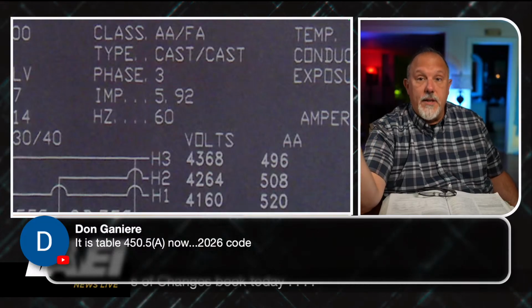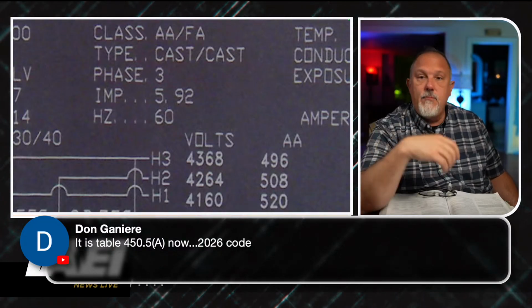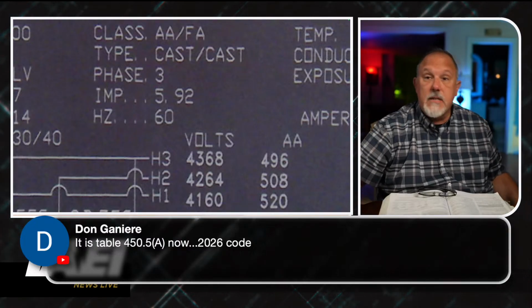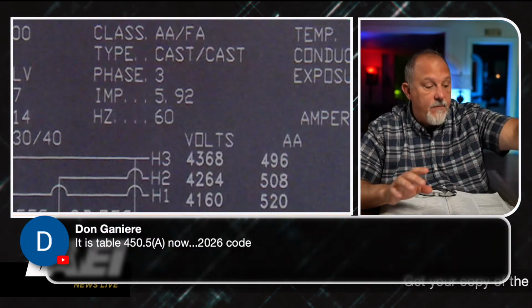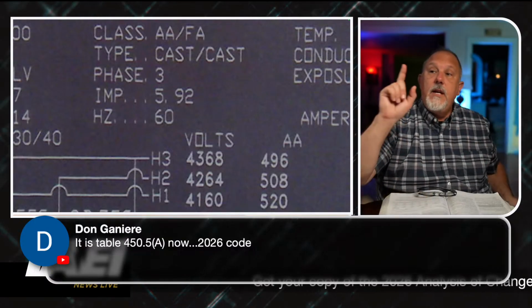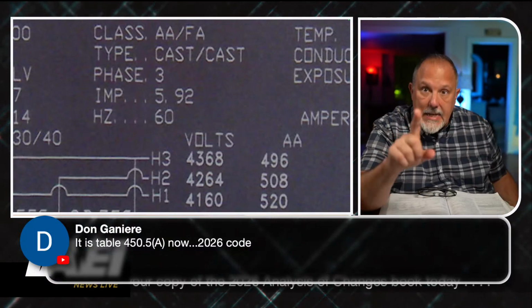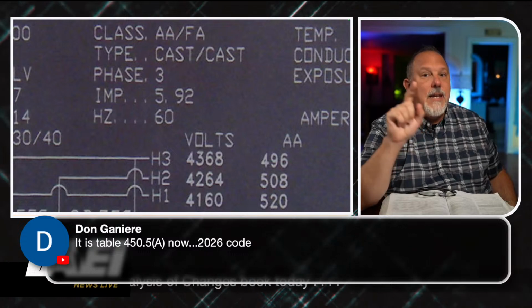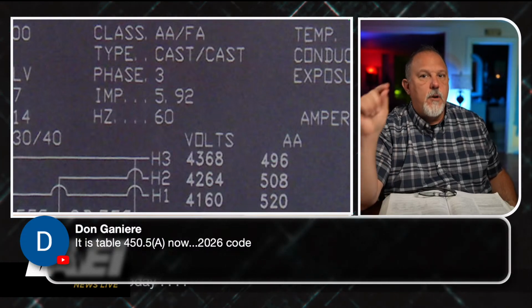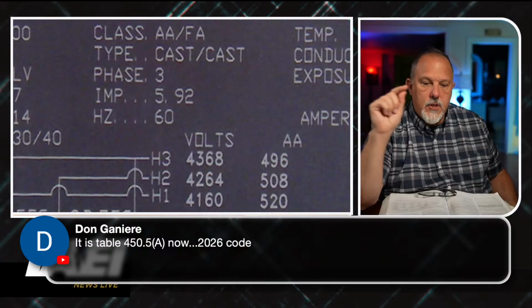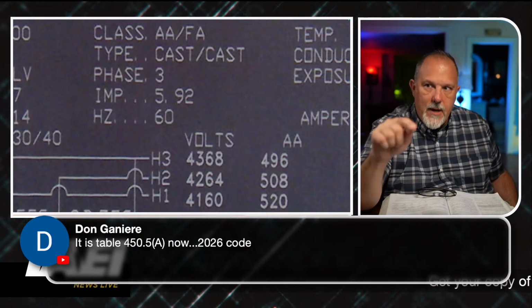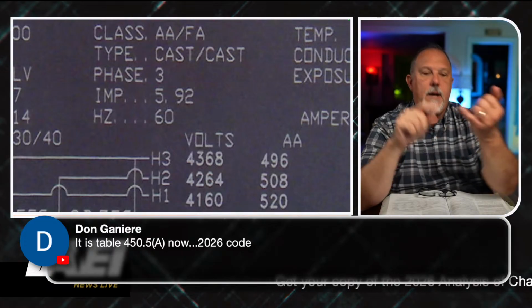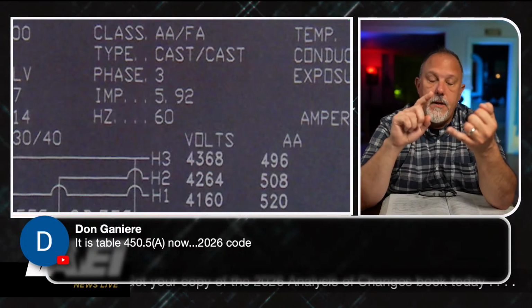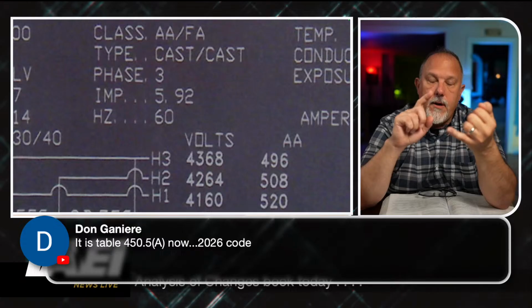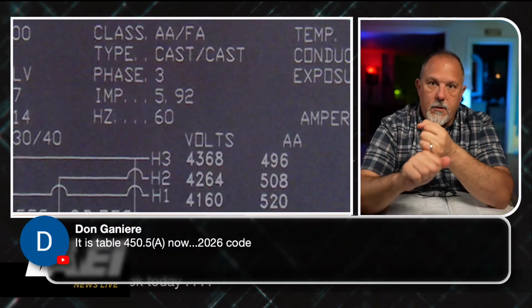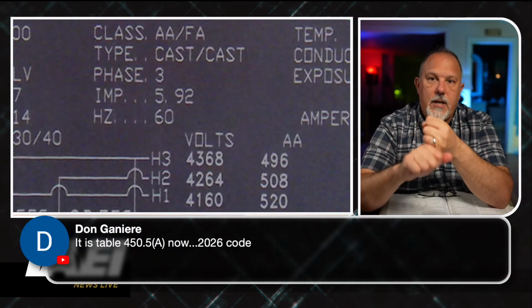Whether or not I cool this thing to be able to add more load to it doesn't make a bit of difference in the impedance. Now, the impedance doesn't change, nor does the inrush current for this transformer change. So when I think about the primary overcurrent protection, what do I worry about? I worry about the inrush current, so I can energize the transformer.